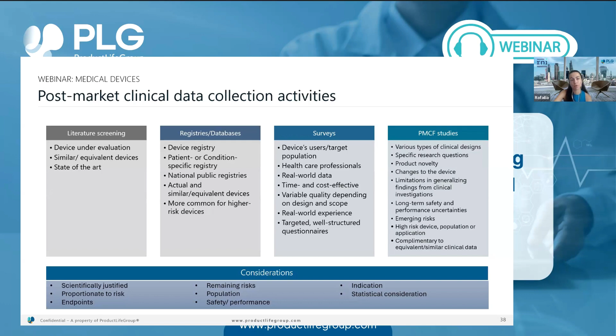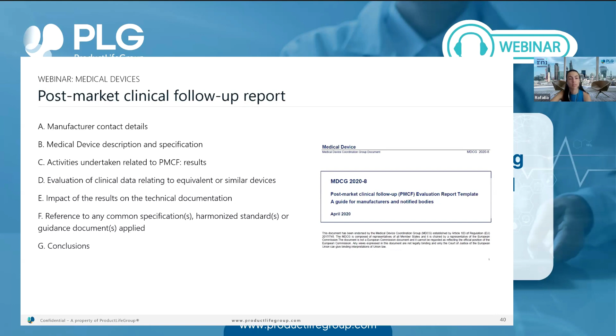This information on post-market clinical follow-up is usually summarized in a plan and a report. There are specific guidances for these documents that provide a structure. However, as mentioned before, you need to provide solid justification, rationale, and explanation, and be specific on the activities that you selected. It is also important that you refer to the technical parts that might need to be analyzed, monitored, or evaluated under the scope of post-market clinical follow-up. And in the report, you will need to summarize all the results, present, analyze, and discuss how they will impact the rest of the technical documentation and what you are going to do about it.